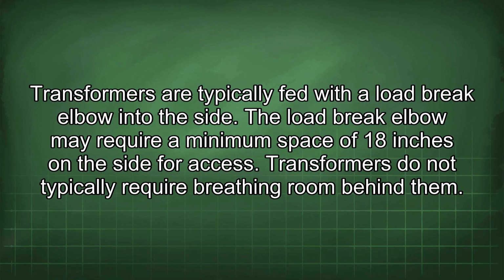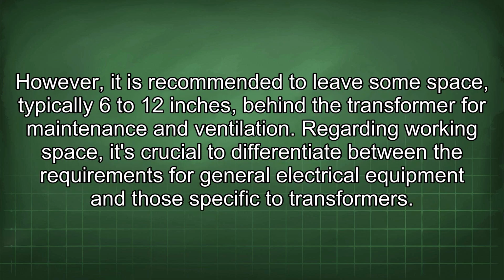Transformers are typically fed with a load break elbow into the side. The load break elbow may require a minimum space of 18 inches on the side for access. Transformers do not typically require breathing room behind them. However, it is recommended to leave some space, typically 6 to 12 inches, behind the transformer for maintenance and ventilation.